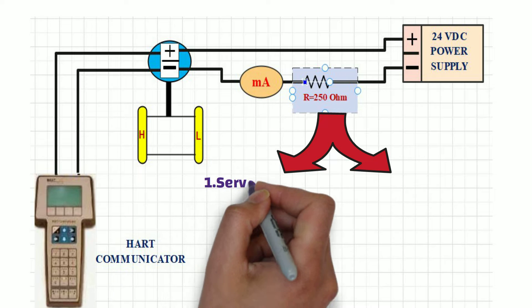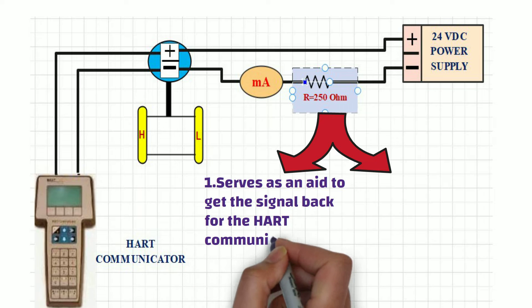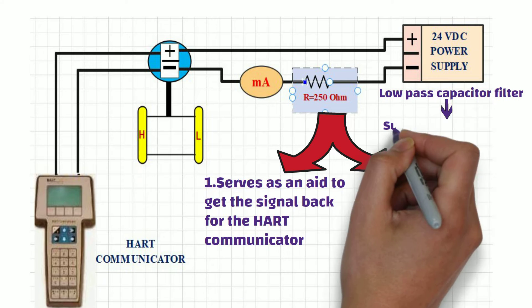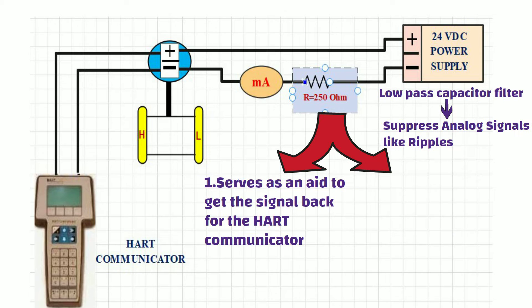Firstly, 250 ohm resistor serves as an aid to get the signal back for the HART communicator. As we know, DC power supply has low-pass capacitor filter which suppress analog signals like ripples. So, if there is no resistance between the power supply and transmitter, analog signal coming from the HART devices will be filtered out. And we won't be able to connect HART device to transmitter in this case.